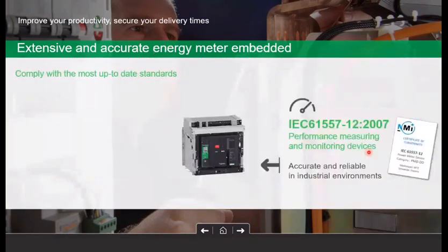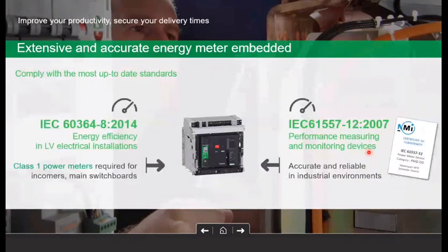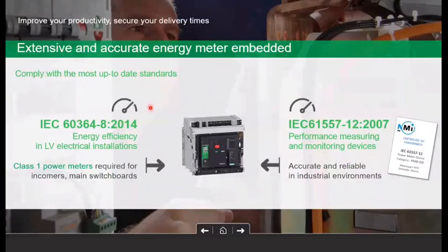If we talk about IEC 61557-12, there are a few more standards which talk about accuracy and energy efficiency in electrical distribution. The second standard is IEC 60364-8. IEC 61557-12 talks about the performance of PMD devices, that is performance measuring devices. I will tell you how MTZ complies with these two standards. It is compliant with this also. I will tell you in the next 2 slides how it complies with IEC 60364-8 also.